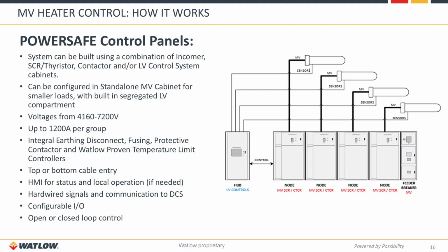And you can do open and or closed loop control, meaning if you have a DCS that wants to operate the system and just give us a duty cycle, we translate that duty cycle into the firing circuit of the heater circuits. We can accommodate that. If you'd like this cabinet to take on the closed loop control, bring a process signal into the particular cabinet, we closed loop control that, control the entire heater sequence based on that closed loop control. The cabinets are capable of doing that as well.